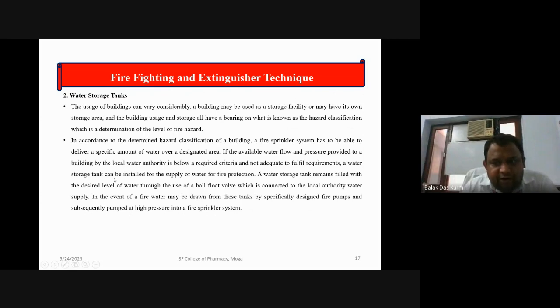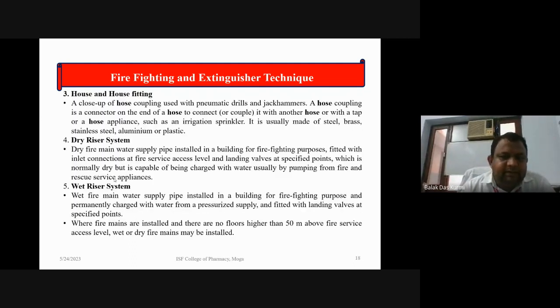If the available water flow and pressure provided to a building by the local water authority is below the required criteria and not adequate to fulfill requirements, a water storage tank can be installed for the supply of water for fire protection. A water storage tank remains filled with the desired level of water through a float valve, which is connected to the local authority water supply. In the event of a fire, water may be drawn from these tanks by specifically designed fire pumps and subsequently pumped at high pressure into a fire sprinkler system.